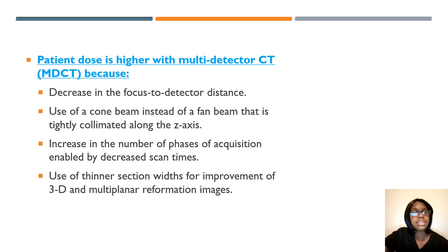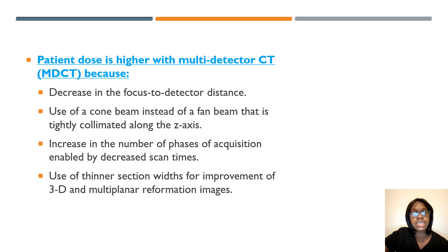Patient dose is higher with multi-detector CT because of the decrease in focus-to-detector distance, the use of a cone beam instead of a fan beam, increasing the number of phases of acquisitions, and use of thinner section widths for improvement of 3D and MPR images.